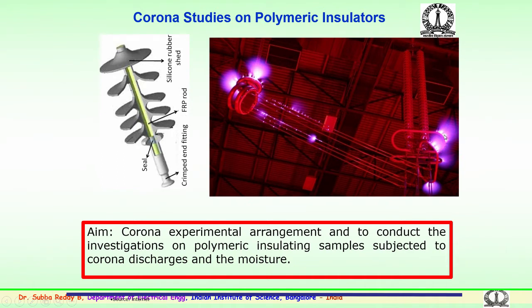The corona which is being generated continuously by the corona control rings will interact with the surface of this insulator, where the continuous bombardment of discharges on the surface is likely to create surface degradation over a period of time. So, how the degradation occurs has to be studied through experimentation.